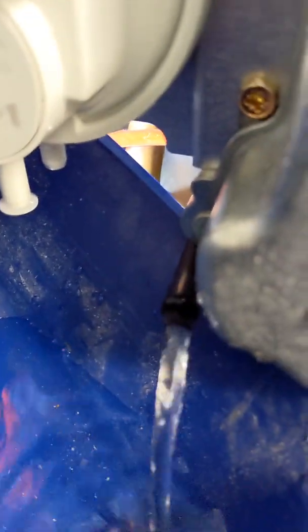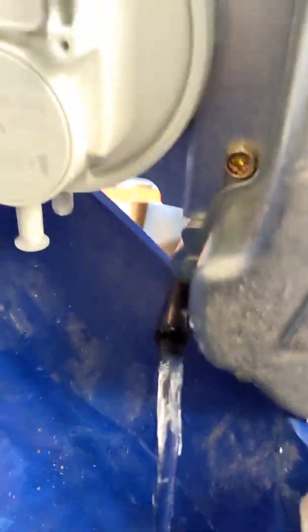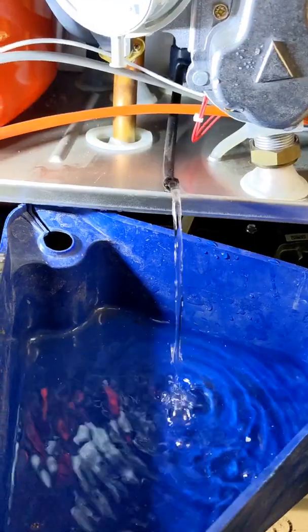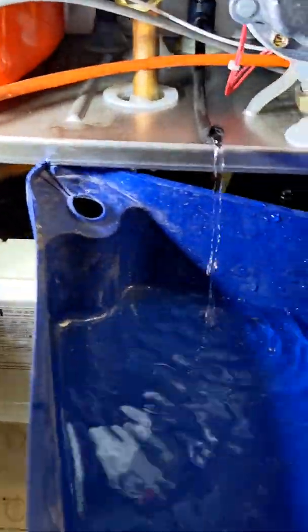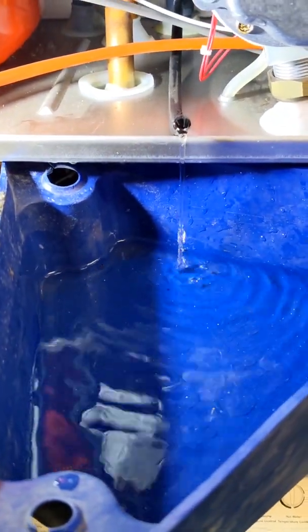And that's what the problem is. Condensate is backing up, and that's stopping the air pressure switch from making and stopping the boiler from firing. That's what's stopping the boiler from firing.